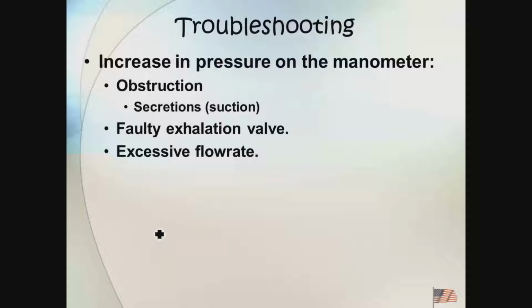Other situation, too much pressure. Duh, maybe there's an obstruction. Maybe there's something that's causing that nasal prong to be blocked up by a bunch of secretions. Not that babies would ever have nasal secretions, mind you. Could be something where that exhalation valve, that thing that's creating the PEEP, is faulty. Or it could be that I have too much flow. Too much flow will actually lead to an elevation in baseline pressure. So it's a dance that you're going to do between too little and too much. You're going to watch the manometer to determine if you've got the proper amount of flow. Make sense? Okay. Guaranteed you'll see a question or two related to CPAP. It's an important concept.